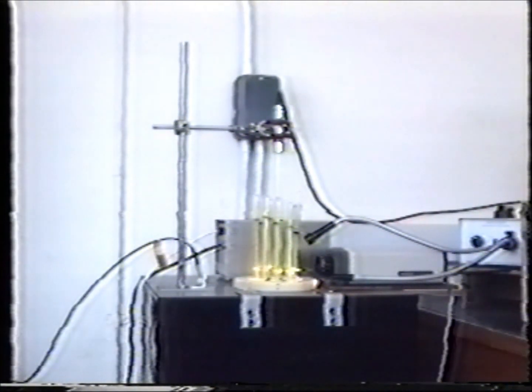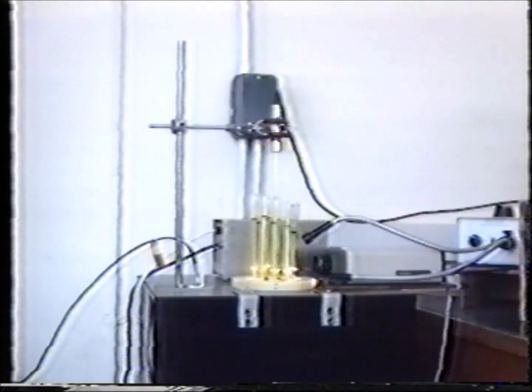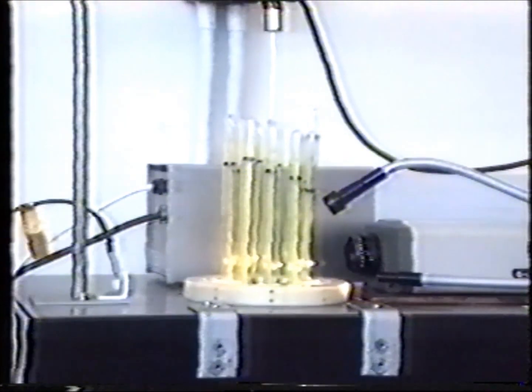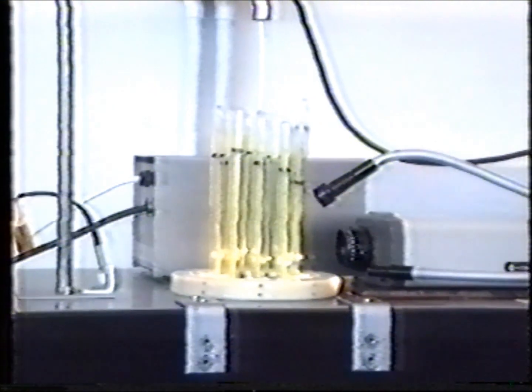Up to 14 thermometers at a time are immersed in a liquid bath held accurately at a specific temperature. They are illuminated by a fibre optic cold light, and a video camera relays an image of the mercury level to a video monitor. The temperature is easily read, and the next thermometer quickly selected by way of the carousel fitted to the bath.